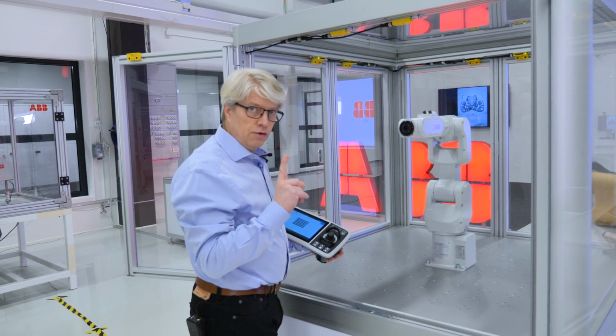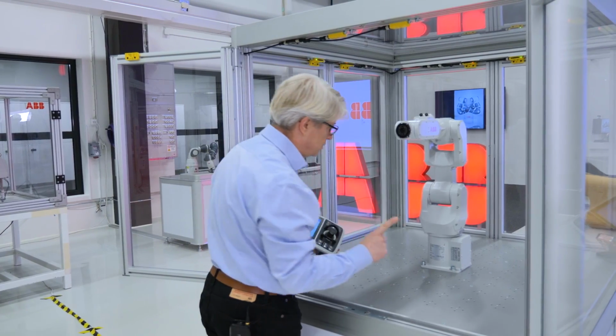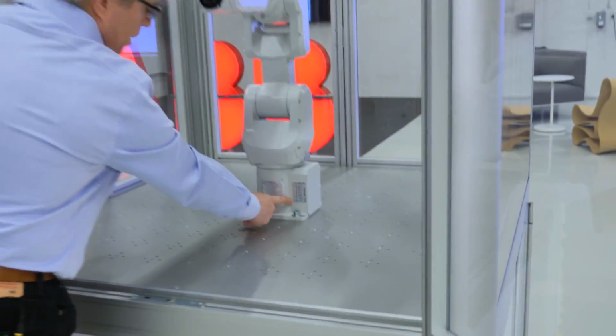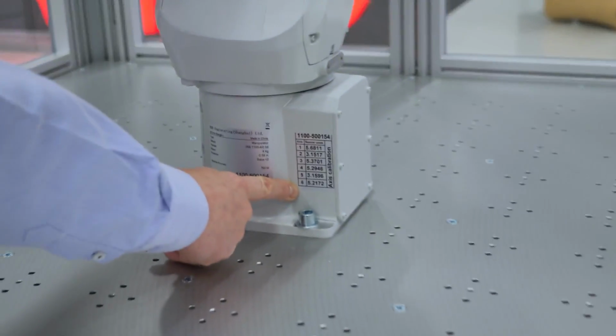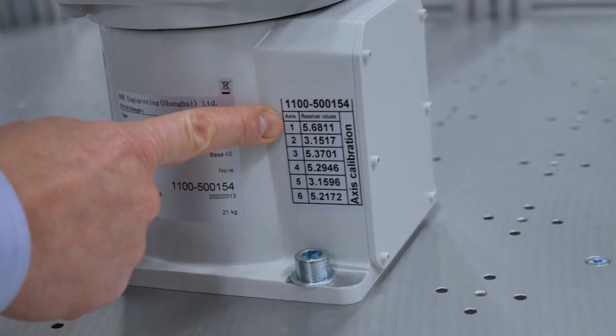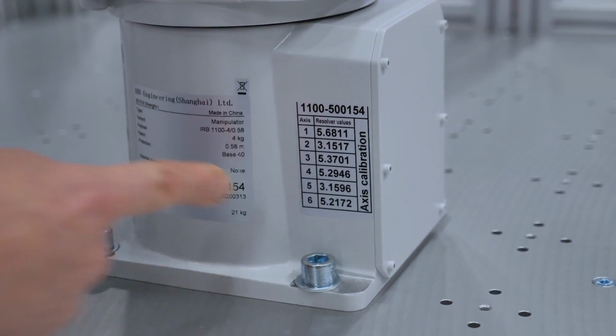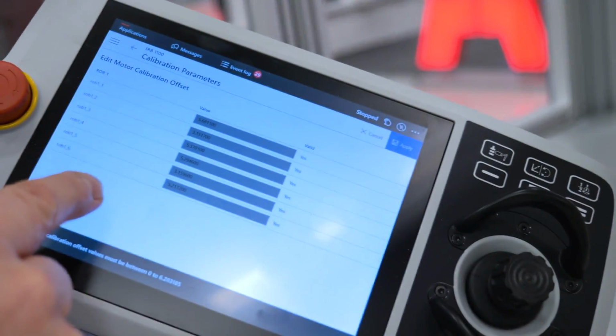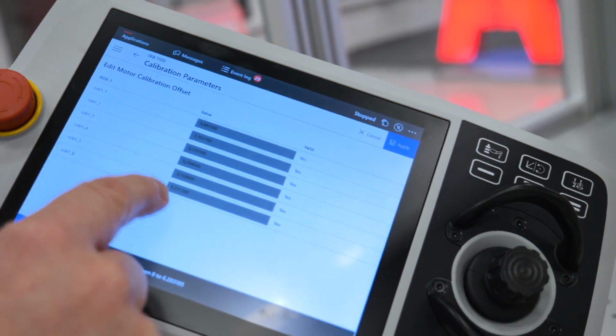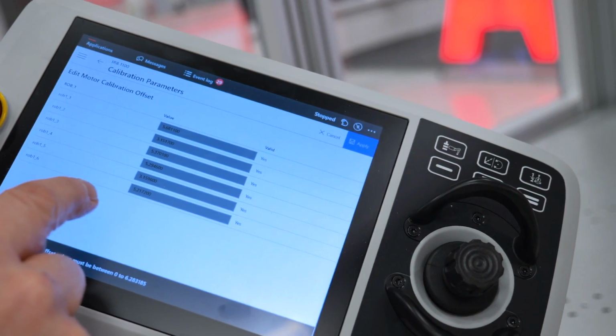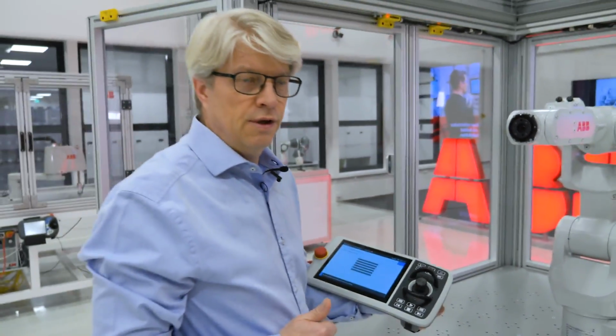Secondly, you need to check the calibration values. On this robot label, you can find the calibration values for axis 1 to 6. If you check the calibration values on your teach pendant, you should see that those are the same values. Then you know that this robot is accurately calibrated and ready to go.